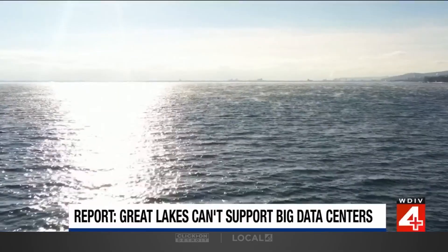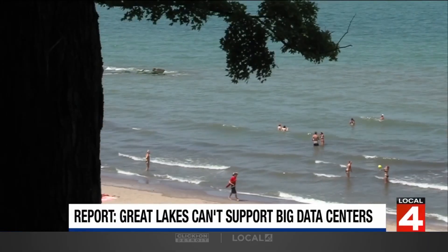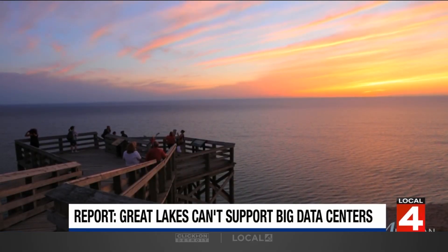This is a really dynamic subject and it's changing daily, but you're seeing in the media that the scale is really increasing. The data centers being cited now are of this hyperscale nature, needed and driven by the need to power generative AI. When I say hyperscale, there's no hard and fast definition, but at minimum in the literature I've seen, it's larger than 10,000 square feet, more than 5,000 servers, and using somewhere between one and five million gallons per day, if evaporative cooling is being used.